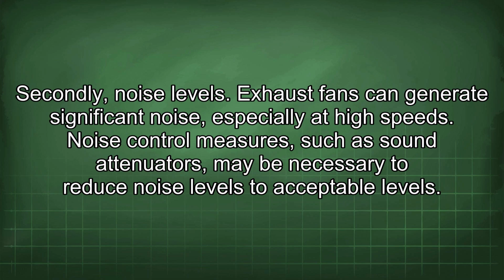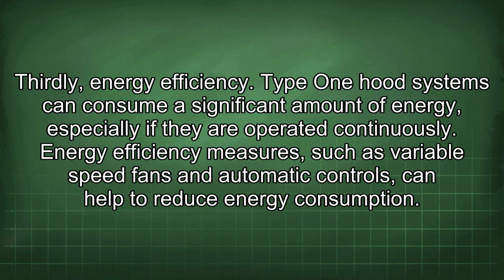Exhaust fans can generate significant noise, especially at high speeds. Noise control measures, such as sound attenuators, may be necessary to reduce noise levels to acceptable levels. Thirdly, energy efficiency. Type 1 hood systems can consume a significant amount of energy, especially if they are operated continuously. Energy efficiency measures such as variable speed fans and automatic controls can help to reduce energy consumption.